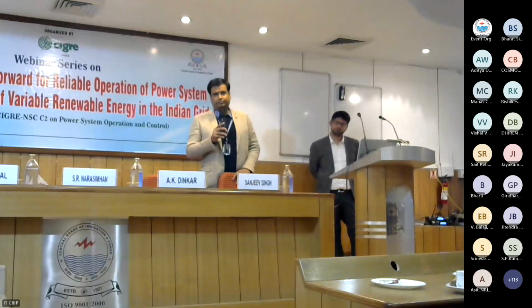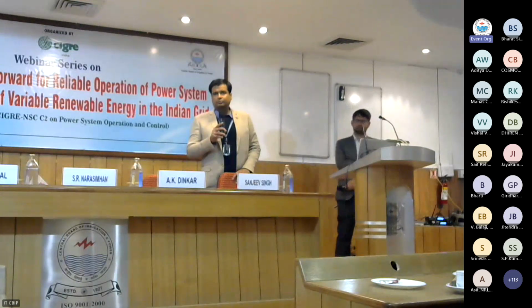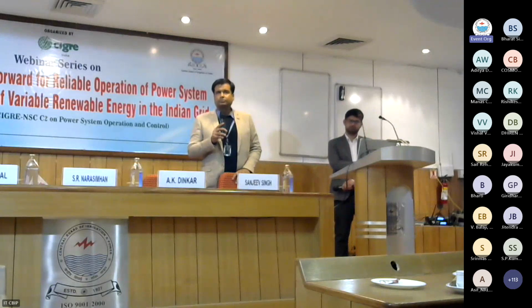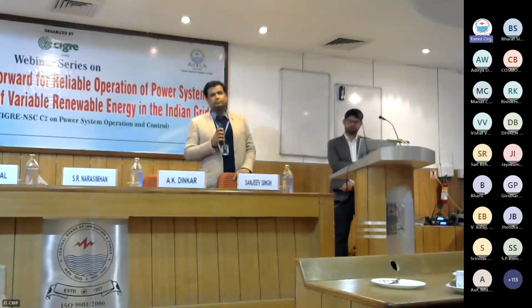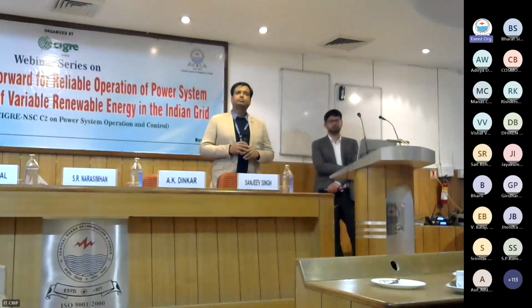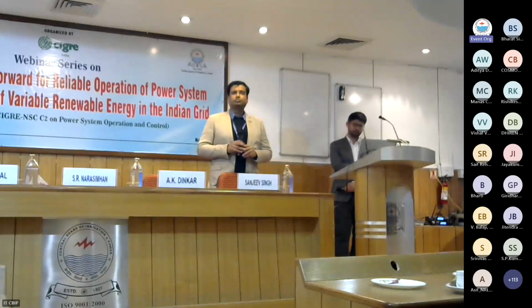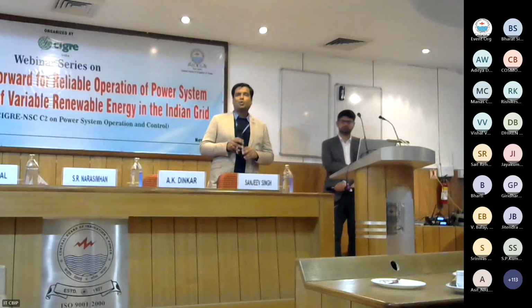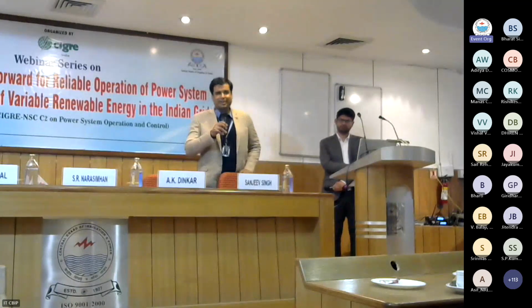No, I understand that. 519, whatever is mentioned, it is applicable. The distribution system, PV penetration is coming in. So on the distribution side, it is required. You cannot apply the same rule of THD calculation on the transmission side and the distribution side. Because in the distribution side, because of various types of inverter, grid forming, swing inverter, central inverter, supra harmonics are coming. New devices are actually measuring, and they are, as per IEC limit, exceeding it. But nobody is having that information, nobody is sharing that information. So we are not the right authority to comment on that.